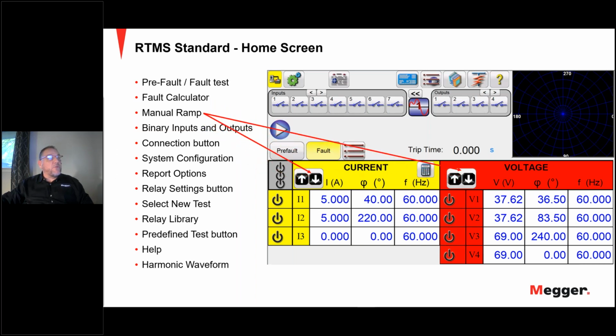Then the next one is the manual ramp. The manual ramp will present the user with a window to select the desired level of increment for manual ramping, the outputs, the desired channels to be ramped, and what is to be adjusted, whether it's the amplitude, the phase angle, or frequency. If using your PC, you can use the keyboard up and down arrows or even your mouse wheel to manually adjust the selected values at the desired increment level.